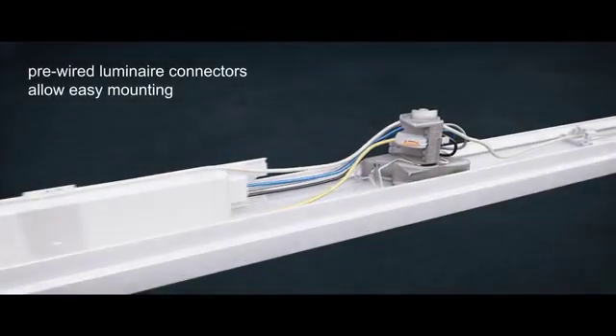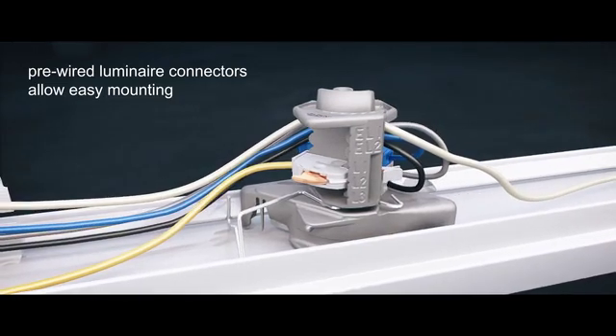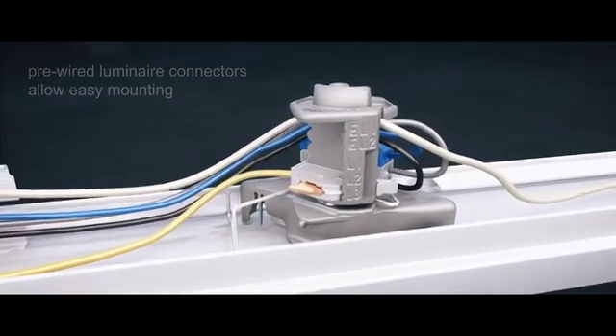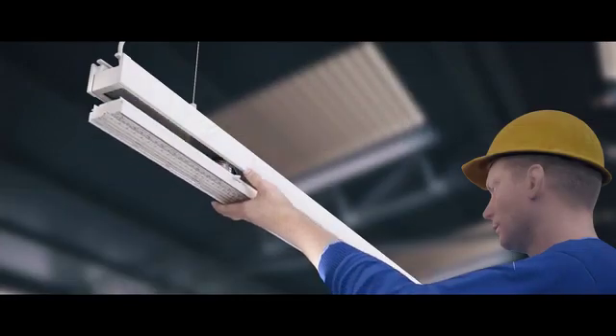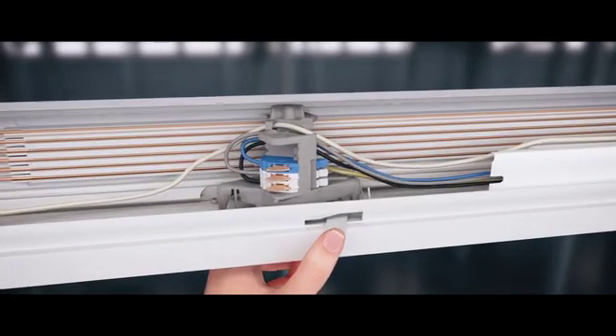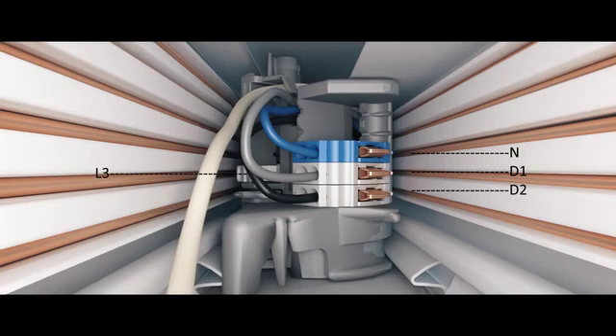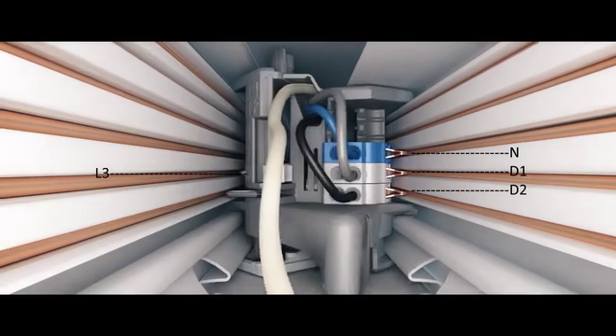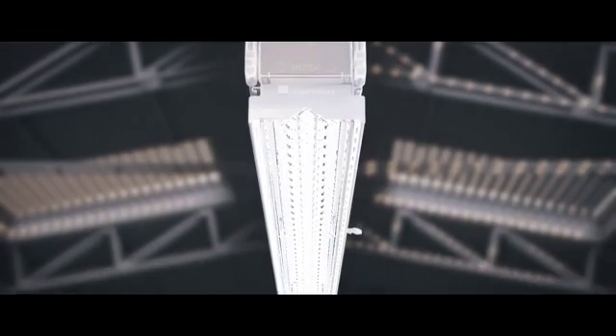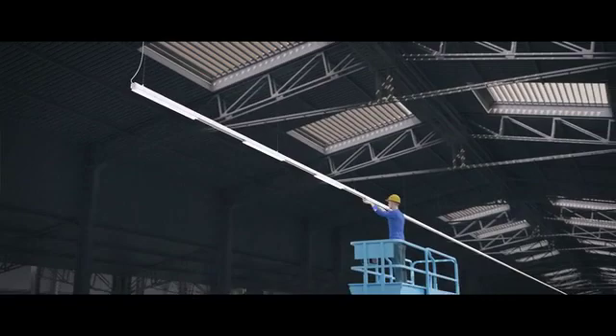The incredible versatility of Tekton lies within its core. Seven poles which provide power and control for the complete system come pre-installed in the trunking. Three dedicated built-in switch legs can be switched individually. Just choose from three different switch legs to easily separate multiple luminaires into switch groups. As a result you get basic lighting control functionality without investing in expensive control systems.